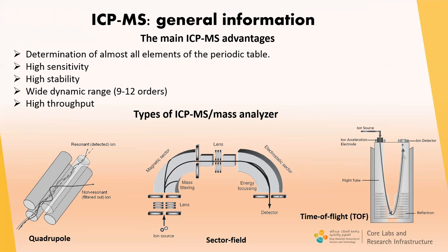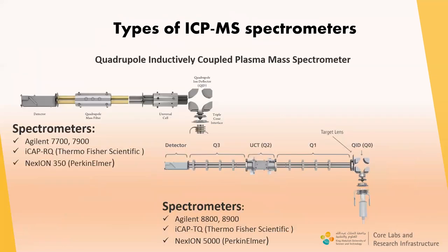There are three main types of ICP-MS instrument design based on different mass analyzers: quadrupole, sector field, and time-of-flight. There are two types of quadrupole ICP-MS spectrometers: single quadrupole and triple quadrupole. In the first type, the mass analyzer includes a collision reaction cell and one quadrupole mass filter. In the second type, the design includes two quadrupole mass filters with the collision reaction cell between them. The quadrupole mass filter allows analysis of ions according to their mass-to-charge ratio, scanning ions in mass sequence from low mass to high mass. The standard configuration of all modern quadrupole ICP-MS spectrometers includes the collision reaction cell.